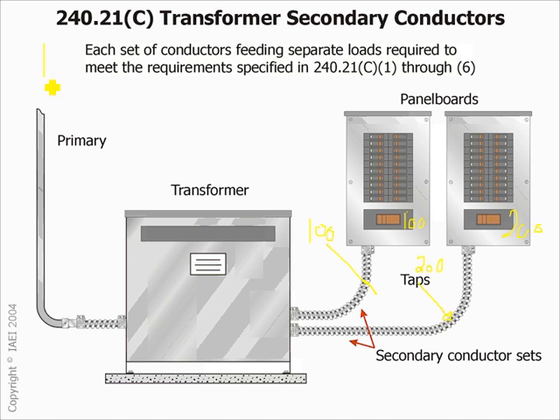Now, here's the issue here. Here's my overcurrent protection device in the second panel, right? You have to have an overcurrent protection device. So what size overcurrent protection device are you going to have here to protect it? Maximum. The problem is always a maximum. Yeah, well, but there's an issue though. There's voltage ratio. So yeah, you have to ratio it. You're absolutely right. If it's 10 feet, you have to ratio it. Here's 480. This is primary 480, right? Secondary 208.